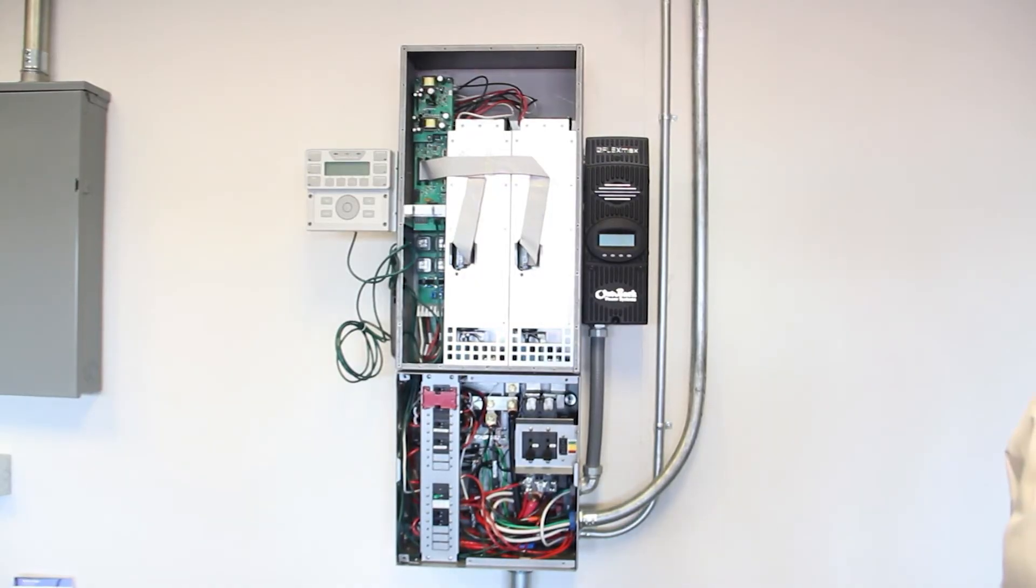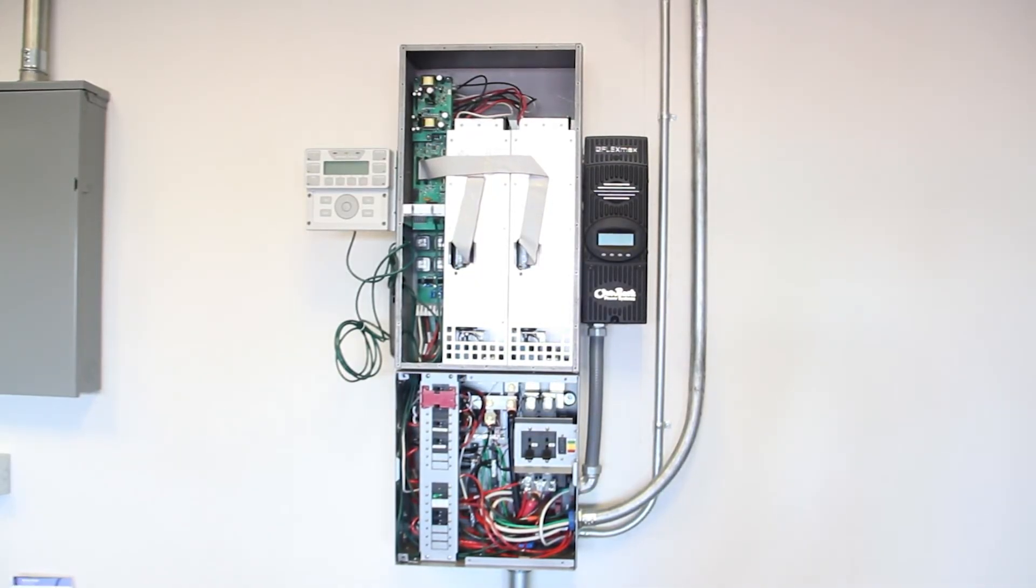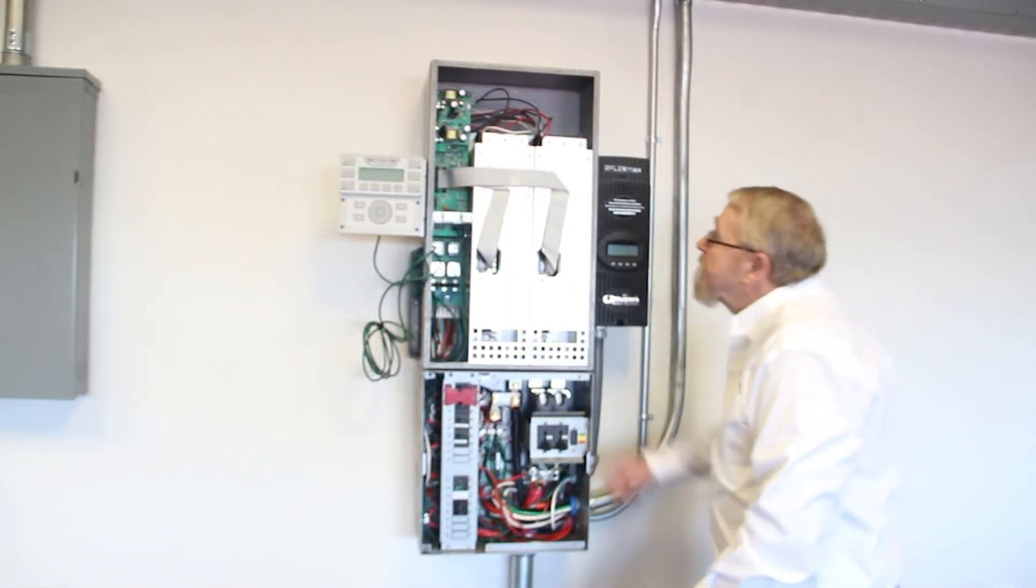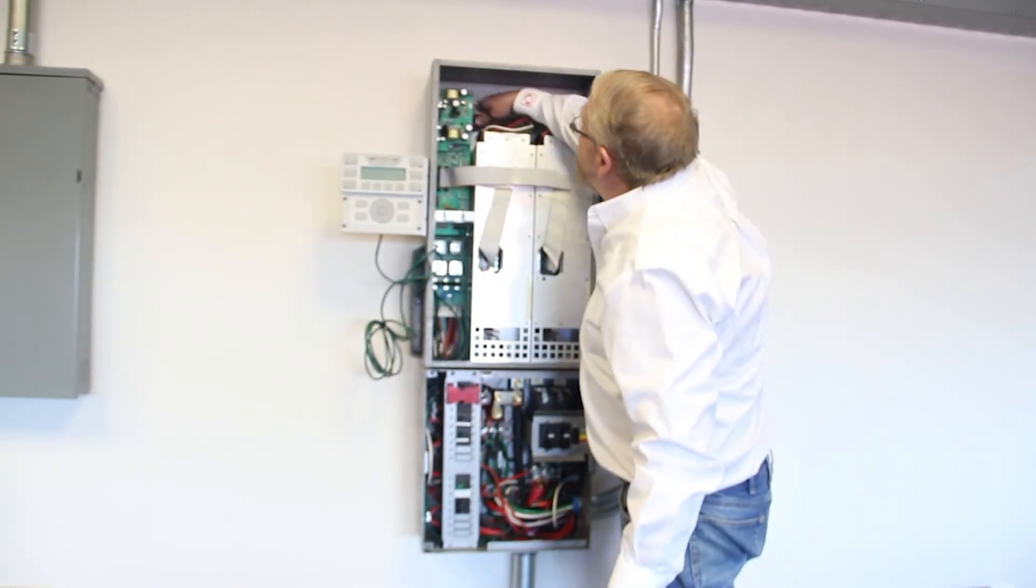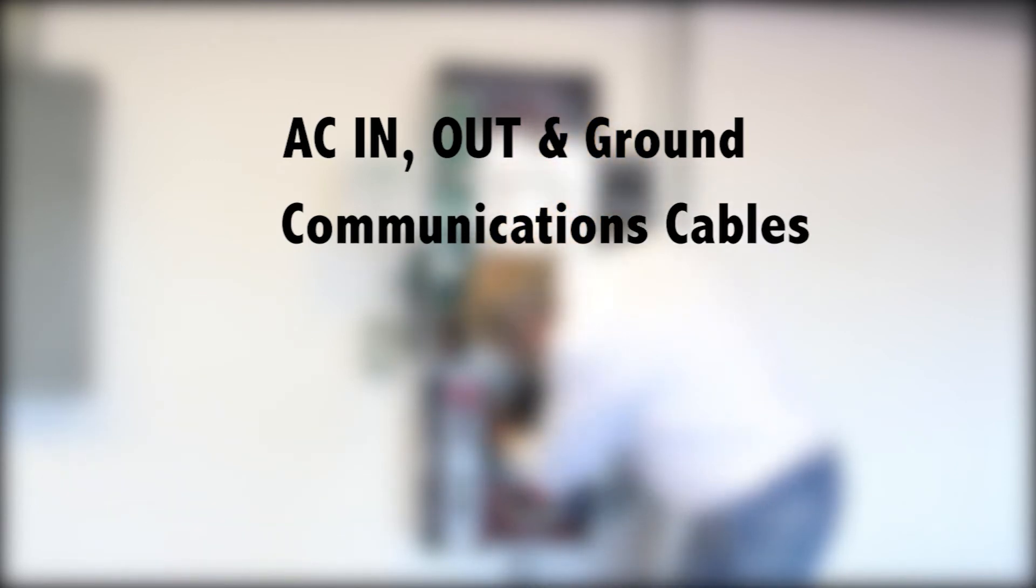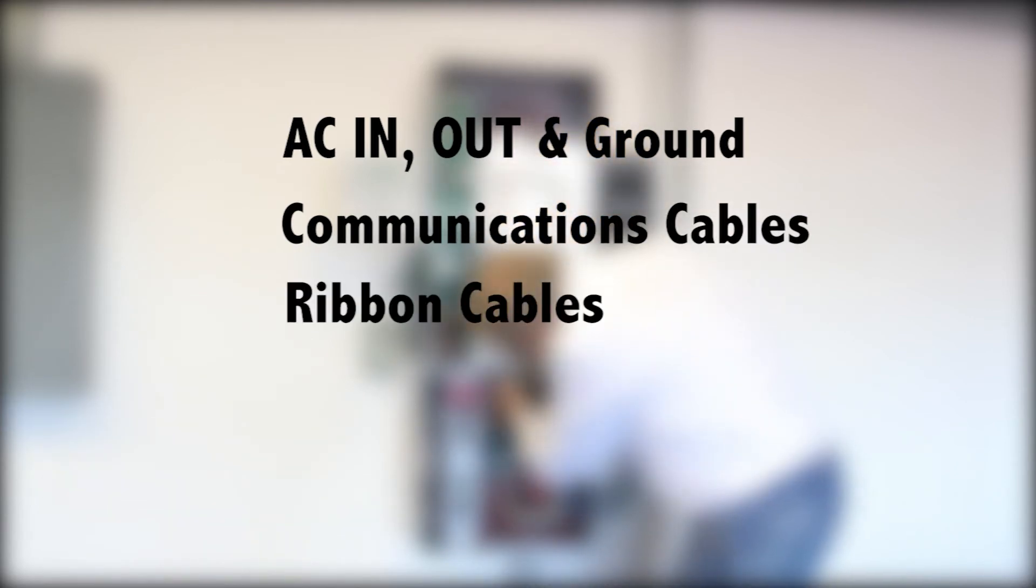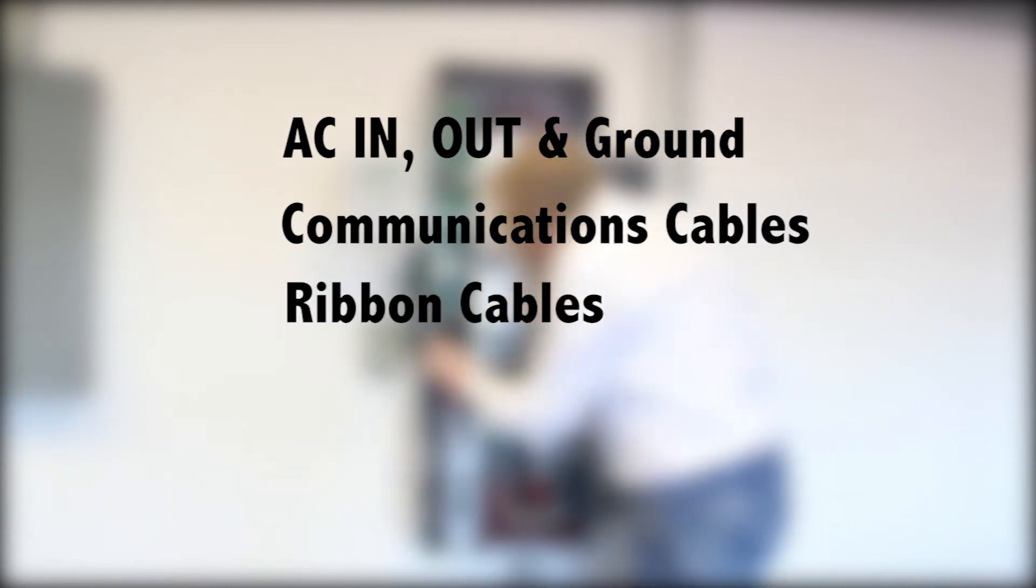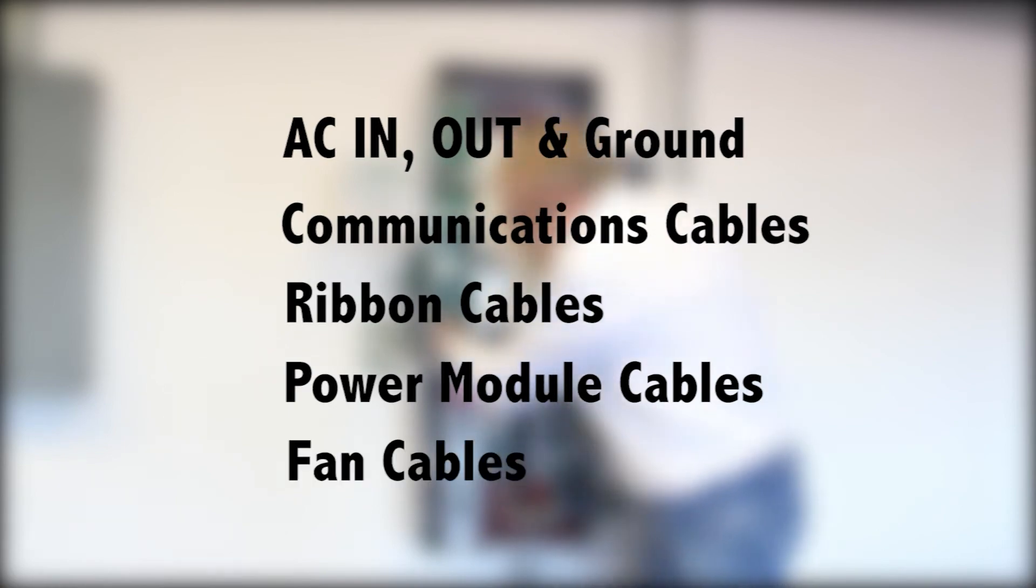Before replacing the front cover, ensure no tools or loose hardware has been left inside the chassis. Also, ensure all electrical connections have been made: AC input, output, ground terminations, communications cable, ribbon cables from both ends, power module cables, and fan cables.